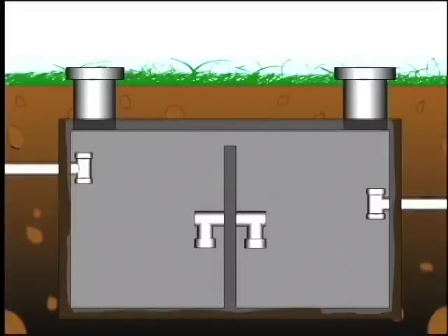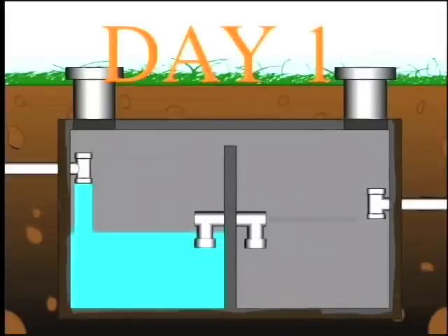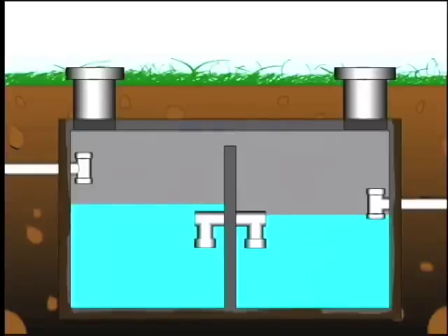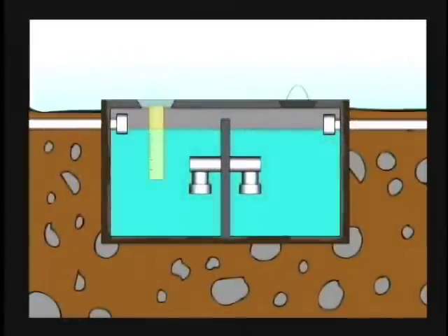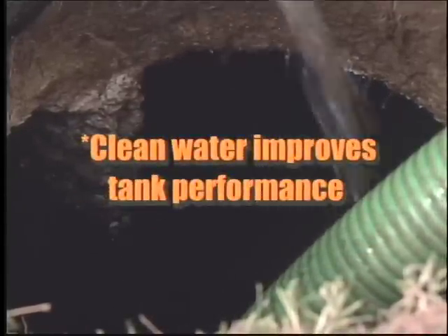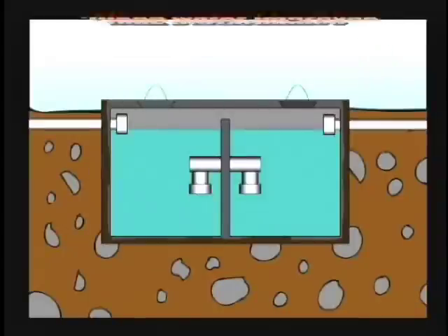A new tank will absorb some water. It is best to fill the tank and, 24 hours later, top off the tank and begin the actual test. Leave the water in the tank, since the tank needs to be full when it is placed into operation. The clean water in the tank improves the tank operation for the first few days.